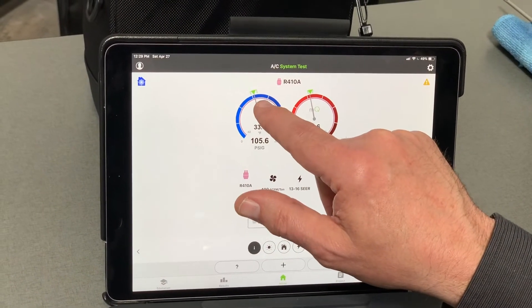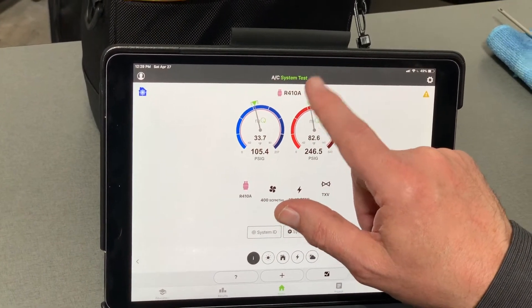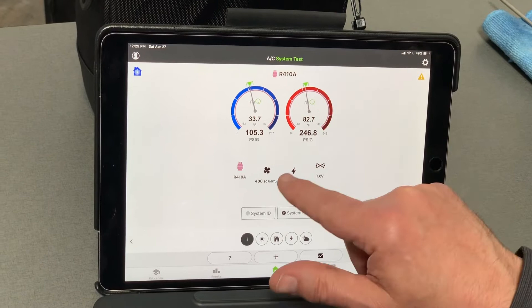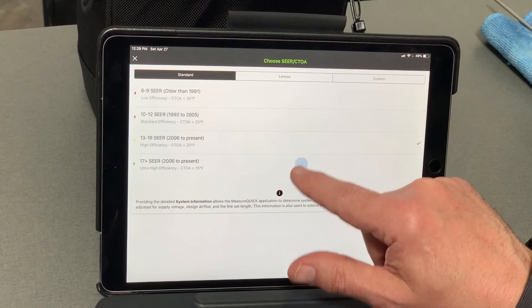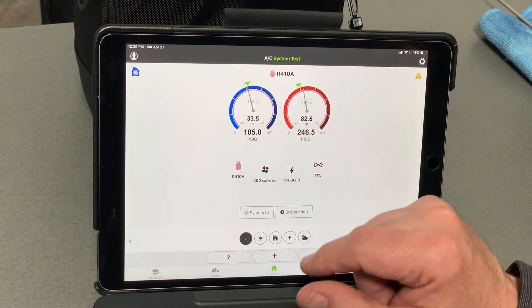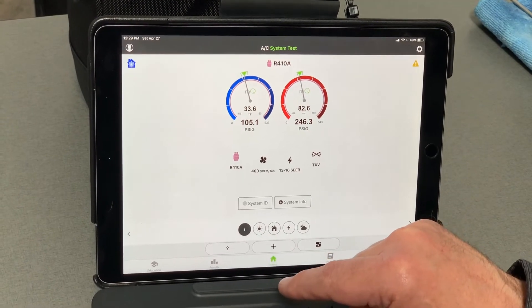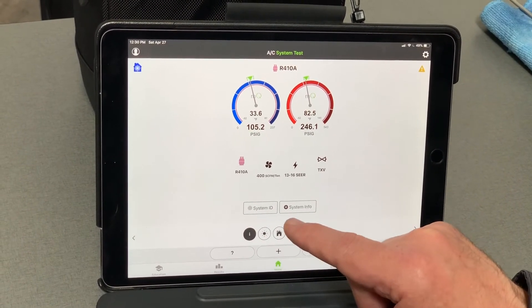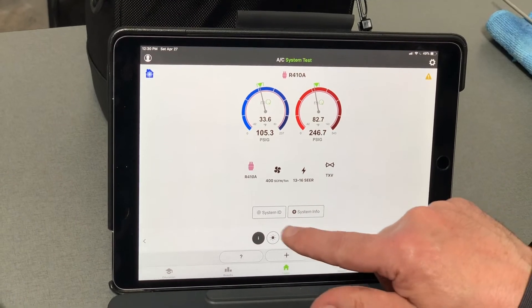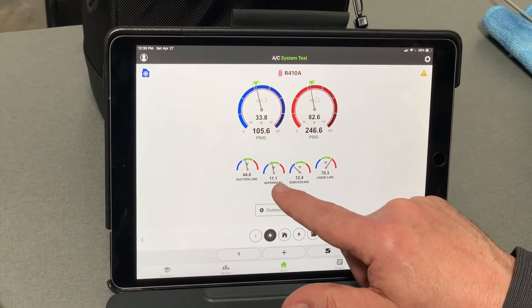Once we have the whole system profiled, we hit submit. This is going to calculate where the pressures should be — you can see my low-side pressure is almost dead center on the target, and same thing with the high-side pressure. Now watch what happens with the wrong profile: if I tell it 17 SEER, the pressure looks too high and the system appears to have problems. Going back to 13 to 16 SEER puts the target right in the right place. These profiling settings are dynamic — they recalculate live — so if the system isn't profiled correctly, you won't get correct readings.